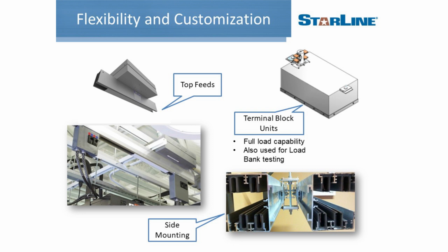We've seen scenarios too where you have height requirements. So that bracket that you see there on the lower right-hand corner of your screen was actually a bracket that we designed for implementation of bus on a Navy ship. As you can imagine, they had deck height issues, and then once the cabinets were installed, there's a very minimal space between the top of the cabinets and the deck height above, and they were looking for an A and B run on a very small envelope. So once again, having that flexibility, that modularity design, and getting a lot of power in a very small space is definitely something that was able to benefit the end user.